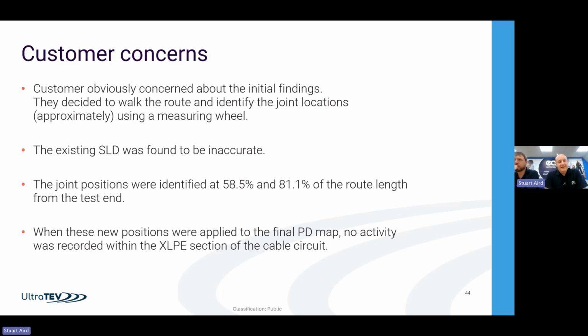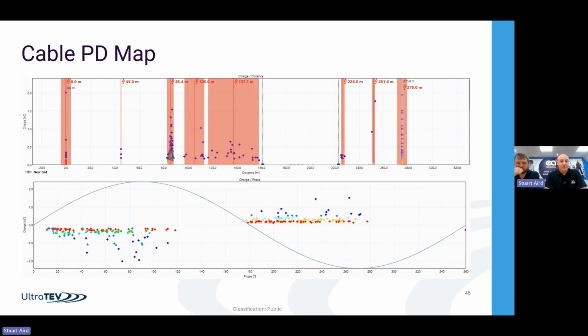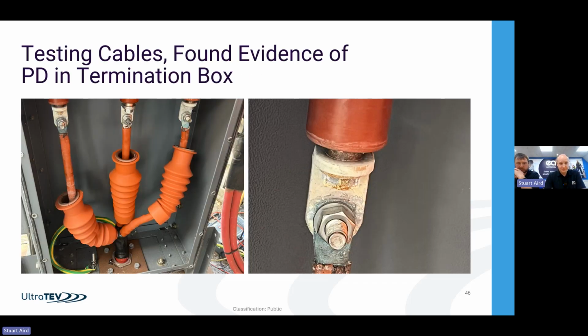And we could then place them back on the map against the data that we'd recorded. So that actually indicated that the PD was in this area, meaning that the actual XLPE section was this area, not the area originally indicated. So the customer was much more reassured that there wasn't any partial discharge now in that area of the cable circuit. But it does show how location of the partial discharge, and obviously checking against customer records, is important when we're doing these cable circuits.